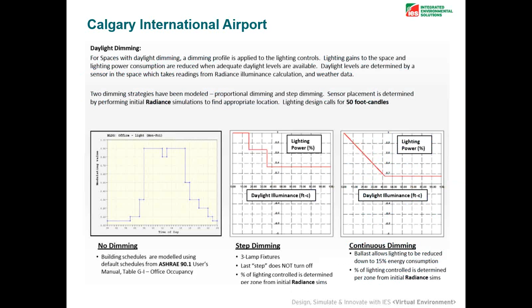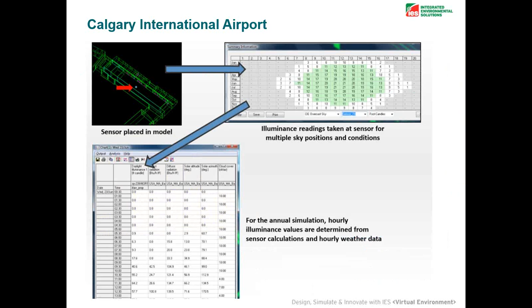So in this case we're setting up a sensor in the space. Once placed, we can run a simulation - illuminance readings are taken at the sensor for multiple sky positions and conditions. The sensor reads, for every hour, how much light it's receiving, and also how much solar radiation is entering the space, and that controls our electrical lighting.